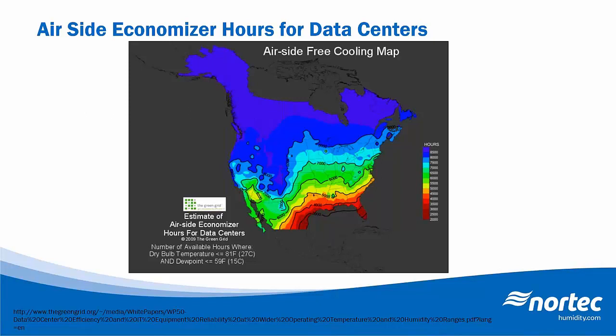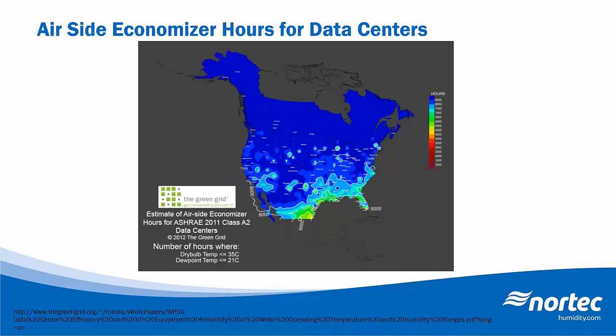The map that we're looking at here is published by the Green Grid, and it effectively illustrates the airside economizer hours based on ASHRAE's recommended range for temperature and humidity. If we look at the map for North America, the dark blue region shows areas that can operate on 100% fresh air economizer for about 8,500 hours out of the year, so effectively the full year. Now, if the IT environmental set points are expanded to the ASHRAE allowable A2 range, you can see that more locations can operate with a higher number of economizer hours here in North America.